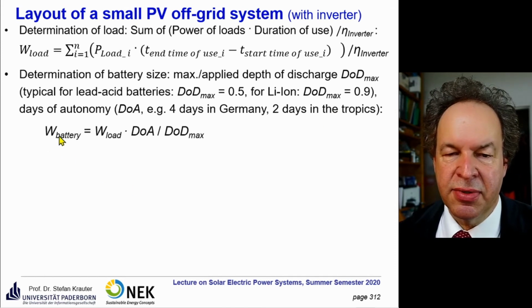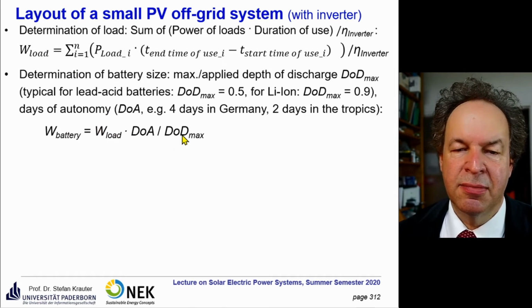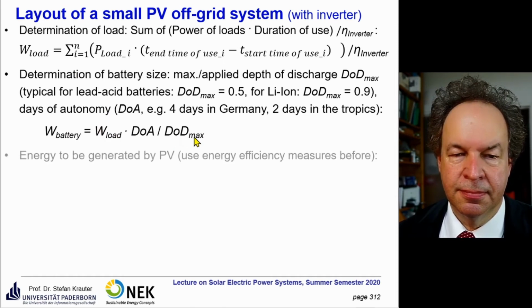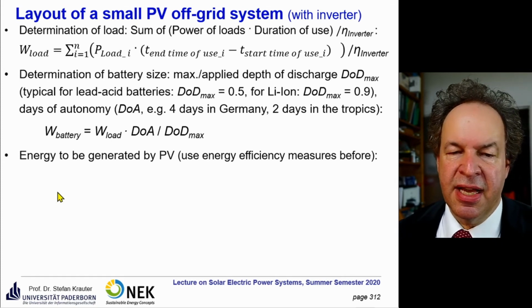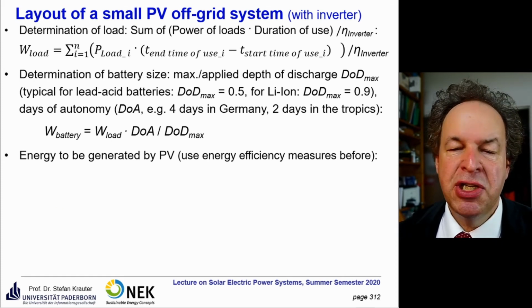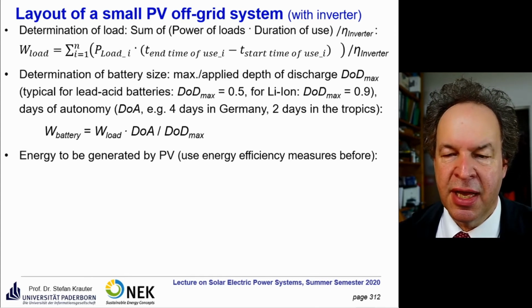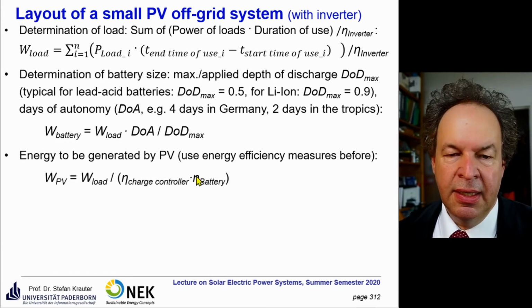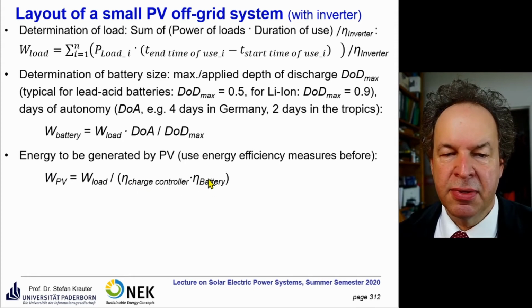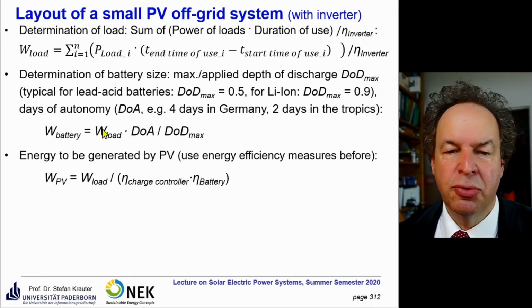So that's the size of the battery. So this is the energy capacity of the battery. This is the energy of the load, what you calculated here, then the days of autonomy divided by the maximum depth of discharge. Then the next step, you come to the energy that has to be generated by photovoltaics to supply the loads, including the losses by the inverter, for example, and the battery. And you see here, the energy to be generated by photovoltaics is the load divided by the conversion efficiency of the charge control and the battery. The inverter is already included in the load here, so we don't have to consider it once more.